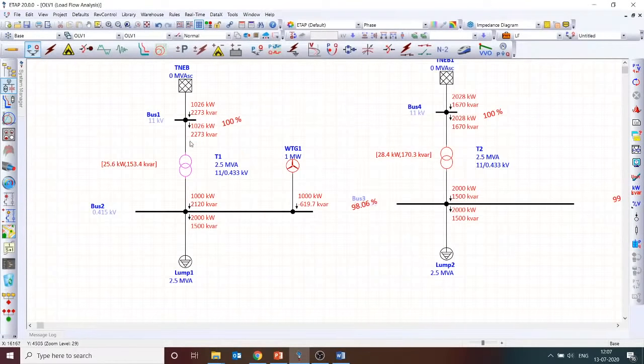So whatever cost you have saved in the energy, you will end up paying as a penalty for a poor power factor. That's because this wind turbine generator is type 1, that is a squirrel cage induction generator, which will not be able to generate reactive power. Instead, it will consume reactive power from the system. So that means you need to add a capacitor bank in parallel with this wind turbine generator to compensate the reactive power consumed by this wind turbine generator.